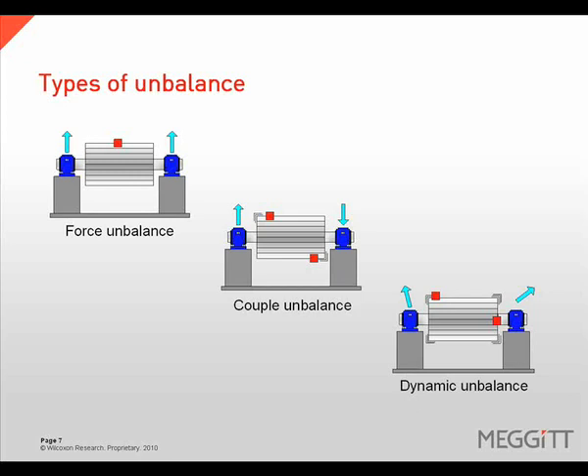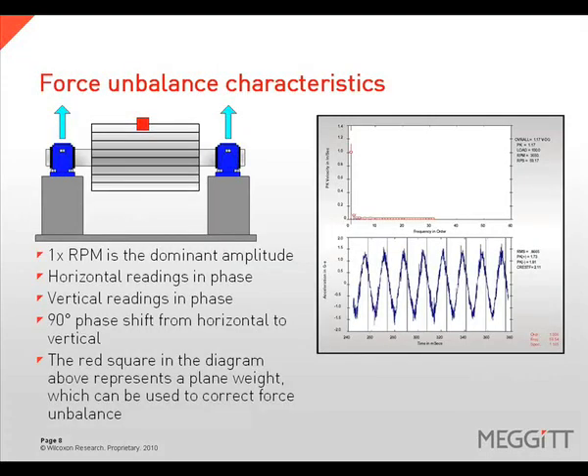The phase is represented in the presentation by the turquoise arrows. Force unbalance will exhibit a dominant 1 times rotational speed amplitude. The horizontal as well as the vertical phase readings will be in phase, with a 90 degree phase shift from the horizontal measurement plane to the vertical measurement plane. This type of unbalance can be corrected with a single plane weight placement.